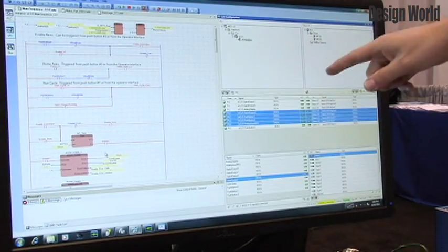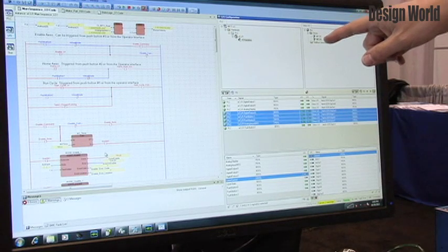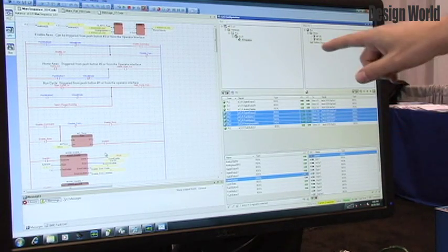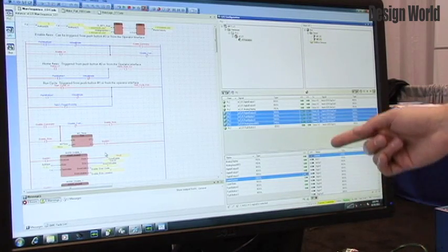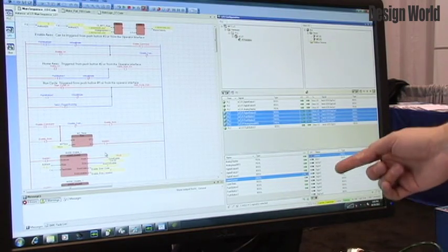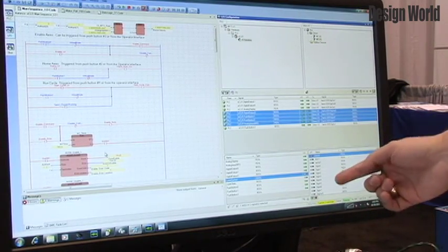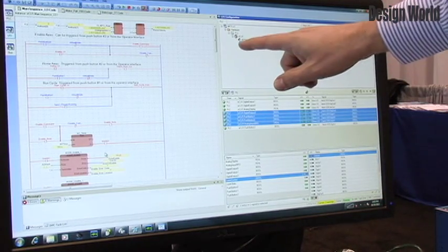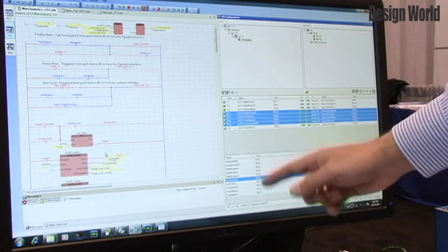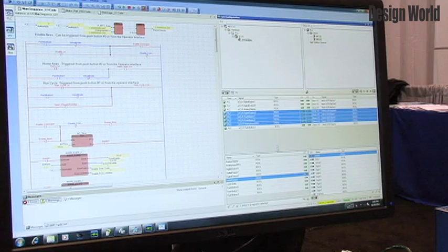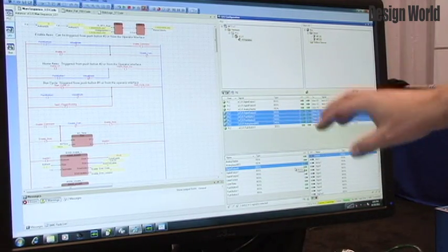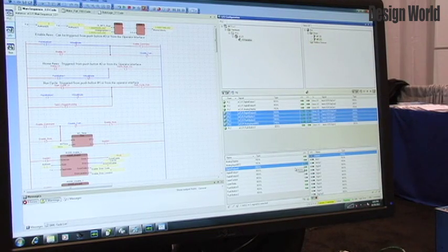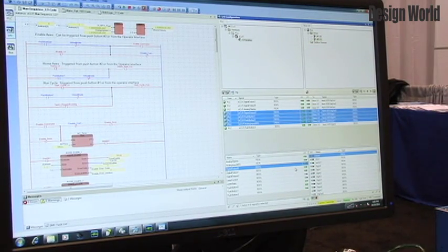You can see here where you have access to all the drives and it automatically will map those to the I/O points. You can see the field buses that you would integrate into the system. All those contacts and signals are displayed here, and then you have all the variables in your program displayed here as well. You can by drag and dropping these onto one another produce all the maps, and this will automatically generate the tag database that all the different programmers and designers would use.